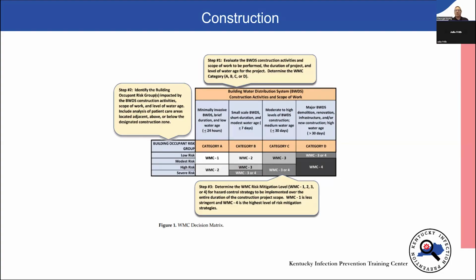In the area they were having an issue, their flow times to reach max temp were greater than 5 minutes because of how that building had been tied in. So although they were providing water at an appropriate temperature with a good residual disinfectant, it was taking so long for fresh water to reach that area that you got biofilm formation, low pressure flow, and related issues.